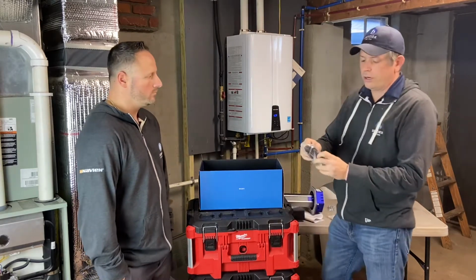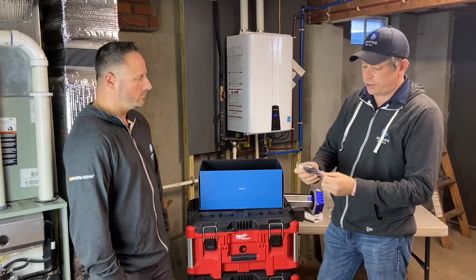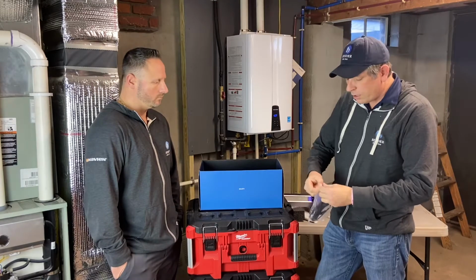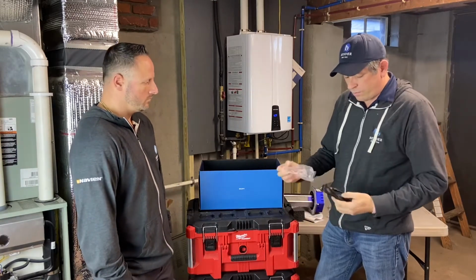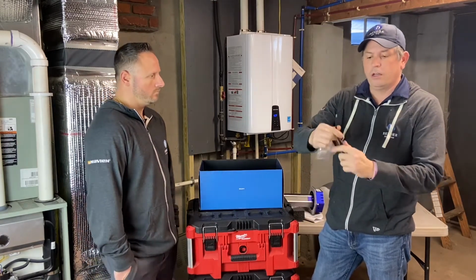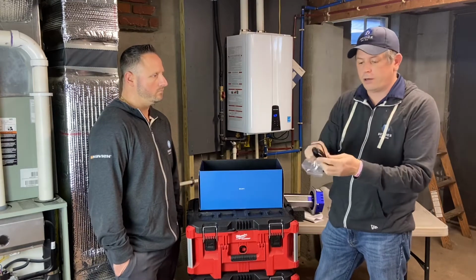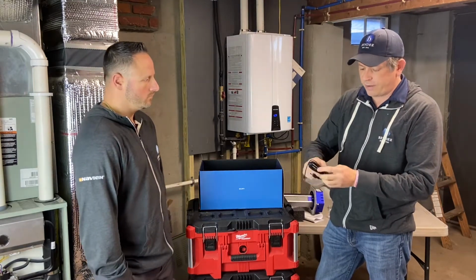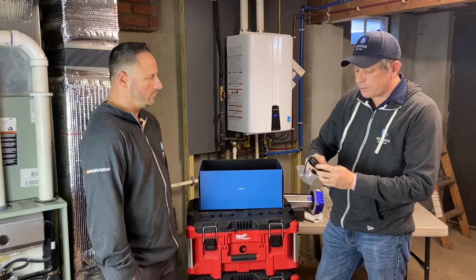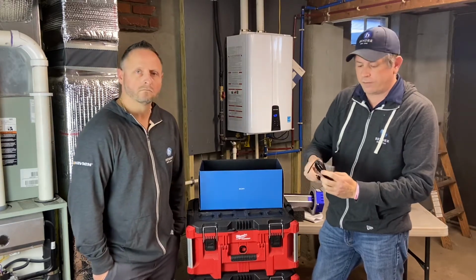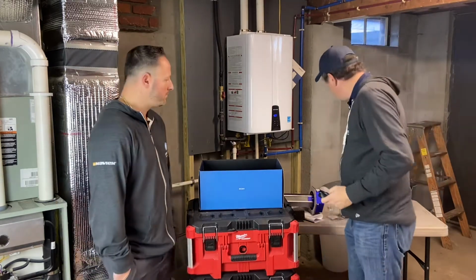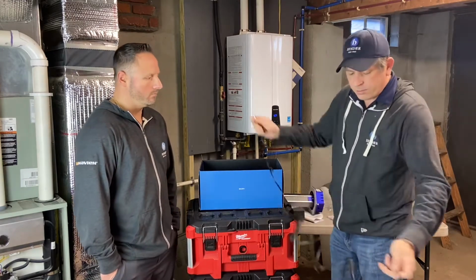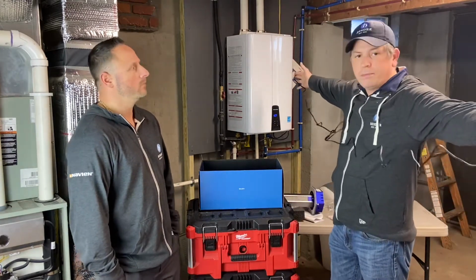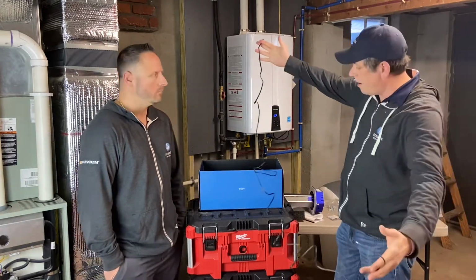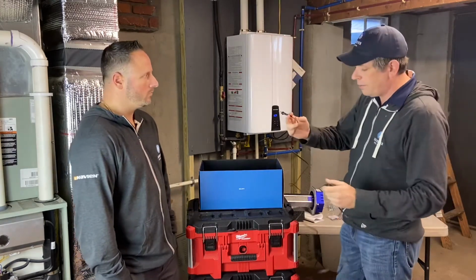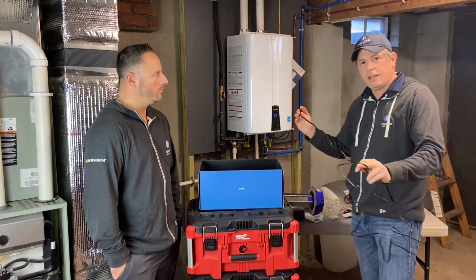Then here's your cord. Once you wire in the transformer, you'll then wire one end of the cord to the low voltage side of the transformer. Over here you have what appears to be about 6 feet of cord - it's probably a little longer, maybe 8 feet - which really helps you put the unit anywhere on the ductwork within reason.